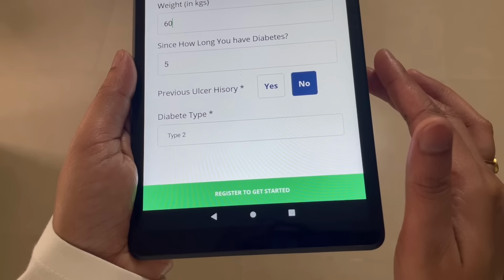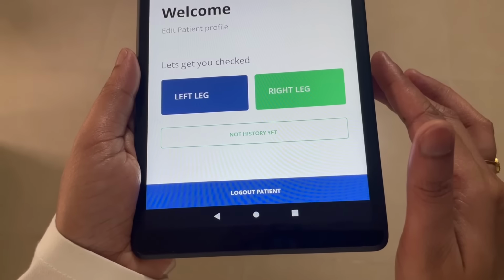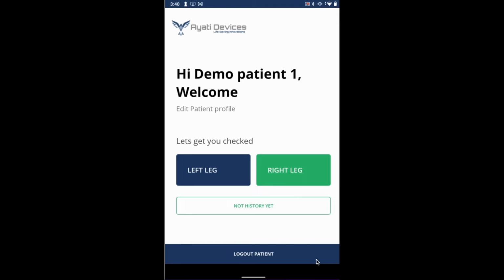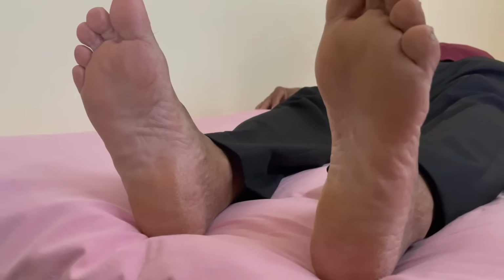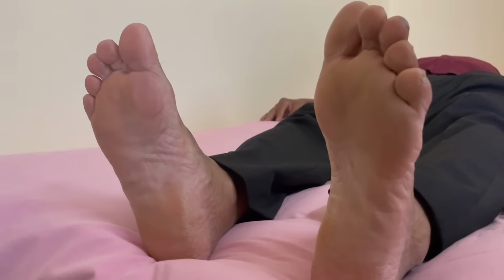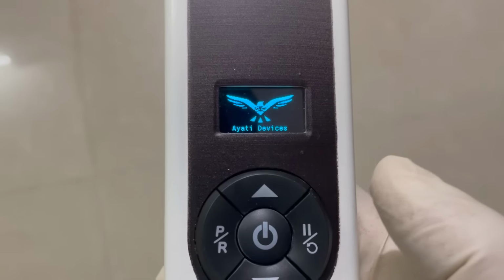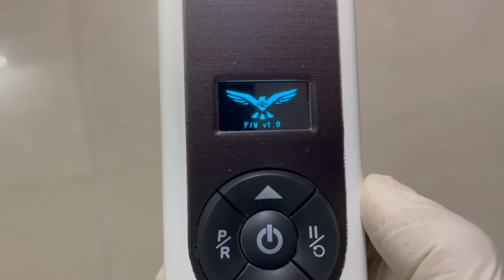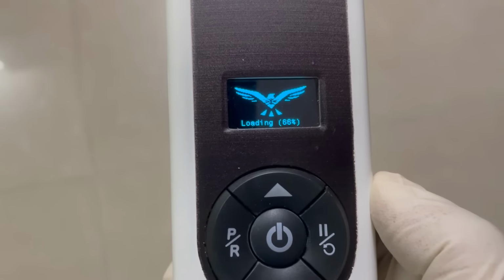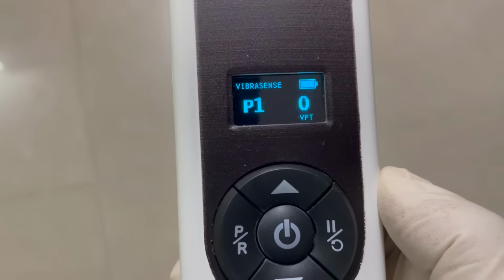You will then get this screen that shows buttons for the left leg and right leg. Do not click on them. You are now ready to start the VPT testing on this subject. Provide the subject a comfortable seat or bed. Turn on the device by pressing the power button. The default screen is on position 1 and VPT 0.